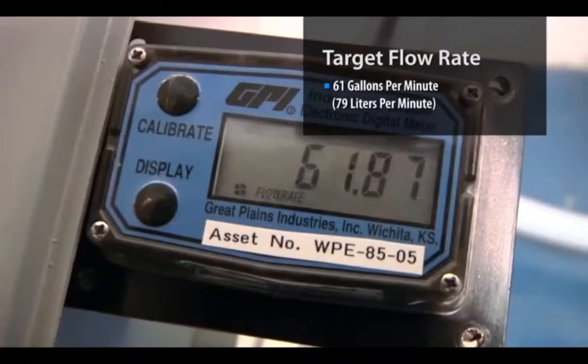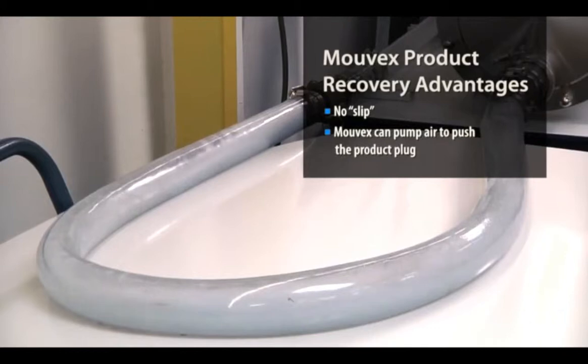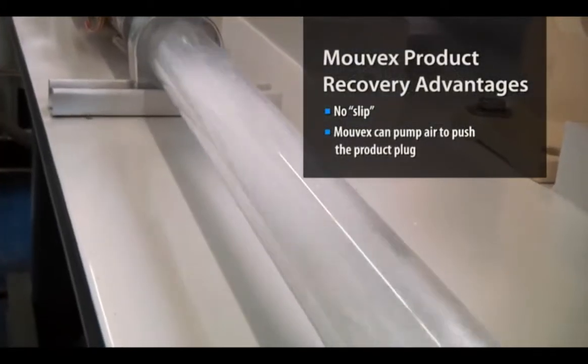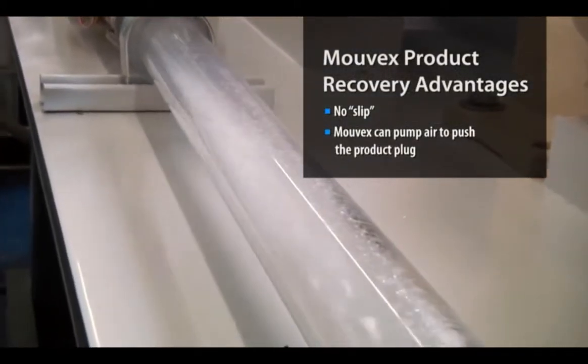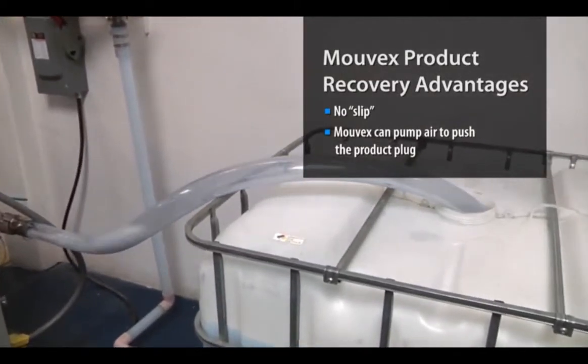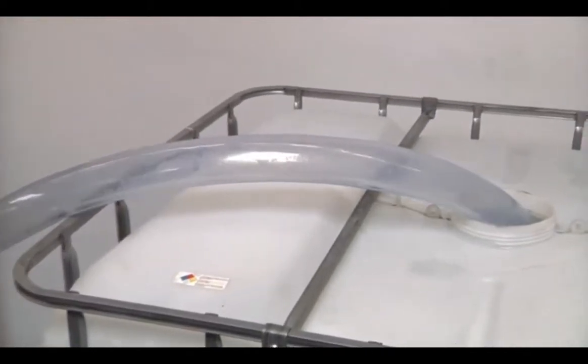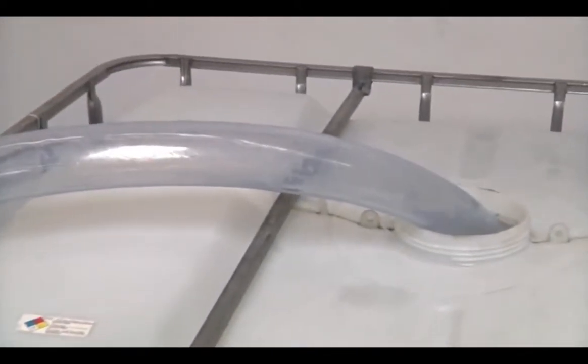For this test, we had a flow rate of 61 gallons per minute. At the end of the process, the Mouvex pump also provides low slip, gradually increasing pressure to literally pump air, then take advantage of the product's surface tension and push the product plug through the tubing, leaving minimal wasted product in the line.